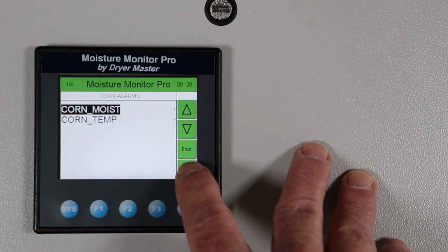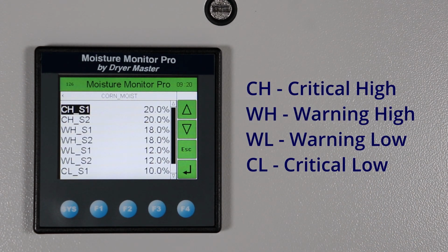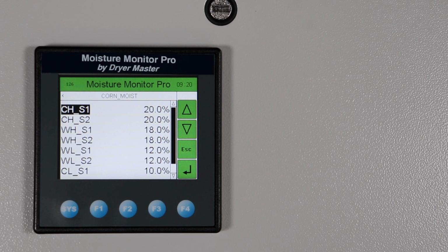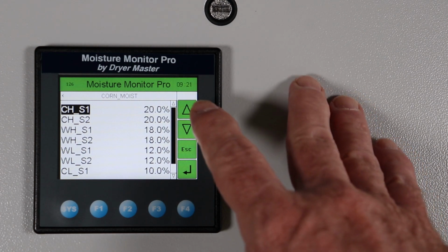So again, it's a touch screen, so we just touch, and then we have 4 settings for each sensor. So we have CHS1, which is critical high sensor 1. CHS2 is critical high sensor 2. WH, warning high sensor 1. And then if we go down, we have warning low sensor 1, WL. And then CLS1 is critical low sensor 1. Now, there's no real difference between anything that happens when you use either critical or a warning. It's just how the information is displayed on the screen that's a difference. So in our case, we're going to look at critical high sensor 1. We're going to change that from 20 to 22.